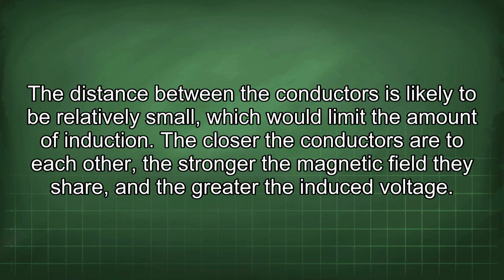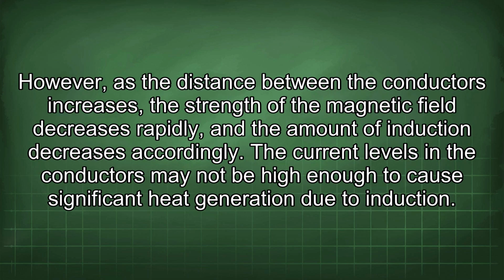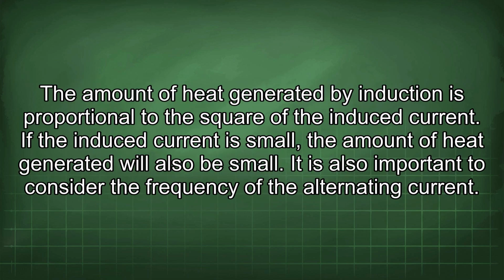The closer the conductors are to each other, the stronger the magnetic field they share and the greater the induced voltage. However, as the distance between the conductors increases, the strength of the magnetic field decreases rapidly and the amount of induction decreases accordingly. The current levels in the conductors may not be high enough to cause significant heat generation due to induction. The amount of heat generated by induction is proportional to the square of the induced current. If the induced current is small, the amount of heat generated will also be small.